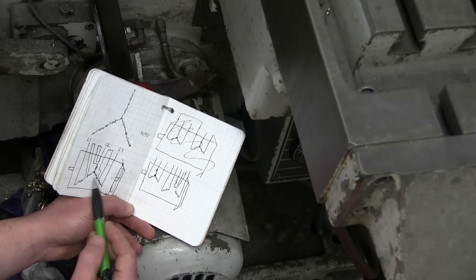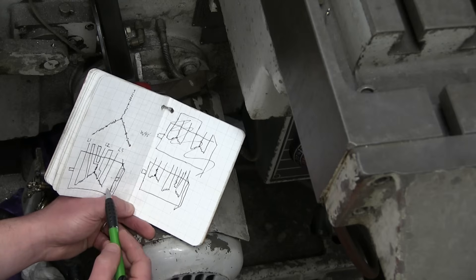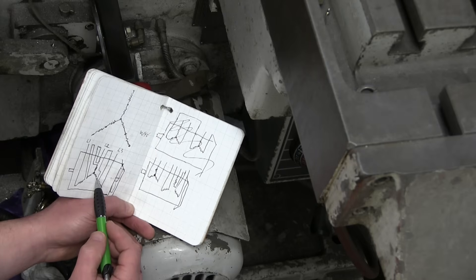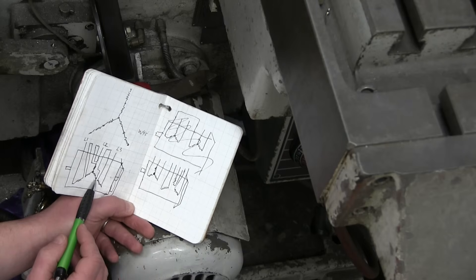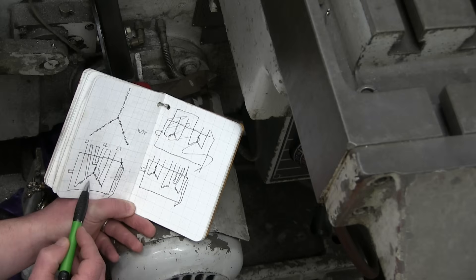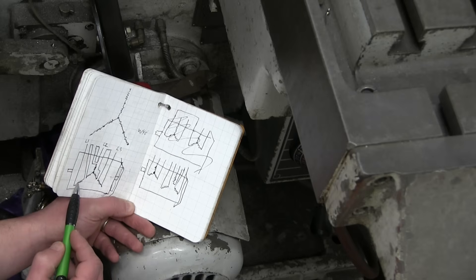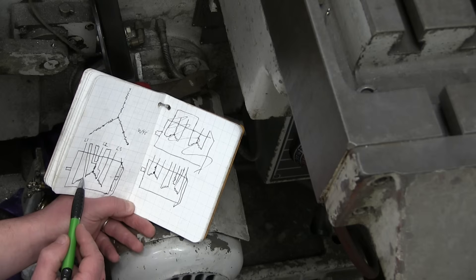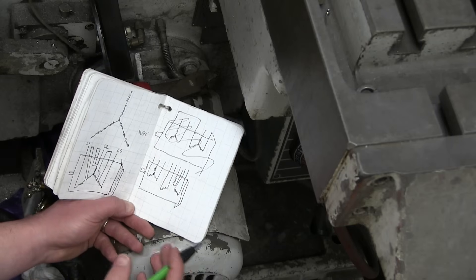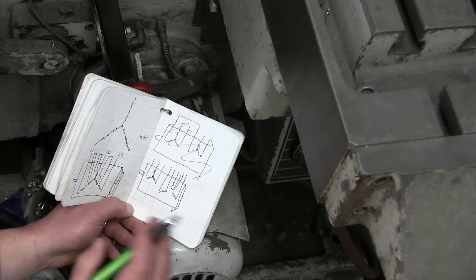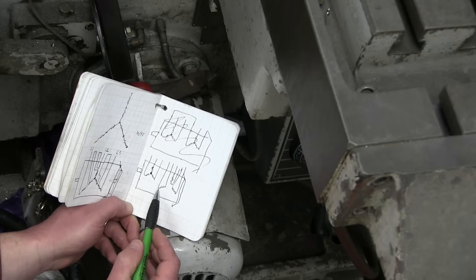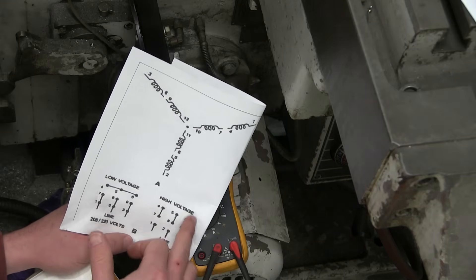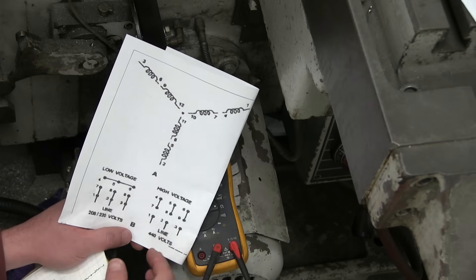The problem here is, because we're relying on the changing magnetic fields to get this thing spinning, if we get the polarity wrong or if we get the phasing wrong, the thing is not going to run proper. It might burn out, it might just not have enough torque. So we need to ensure that we take each one of these out individually and we keep the phasing. So if this point here needs to be connected with this point, this point needs to be connected with this point, because if this point gets connected with this point, the magnetic fields are going to be fighting each other. They're going to be opposite. So we really need to take care and measure properly so that we get the phasing correct.